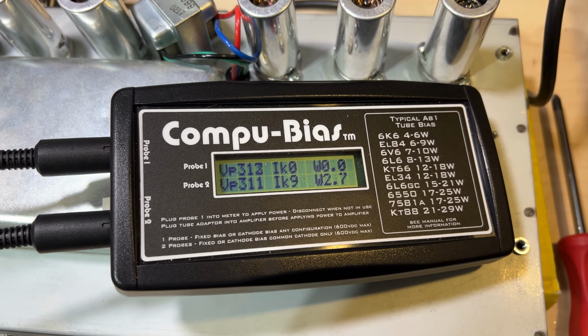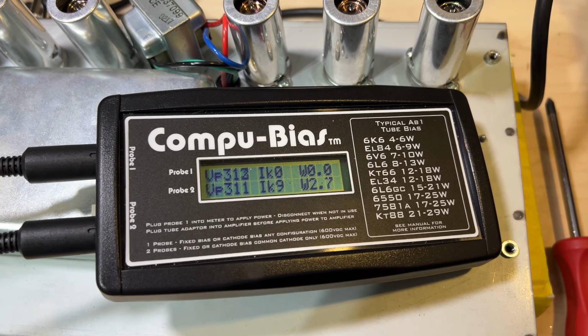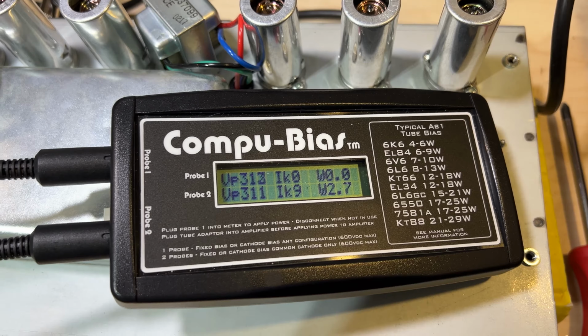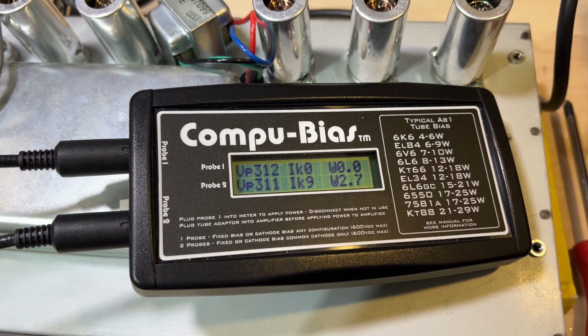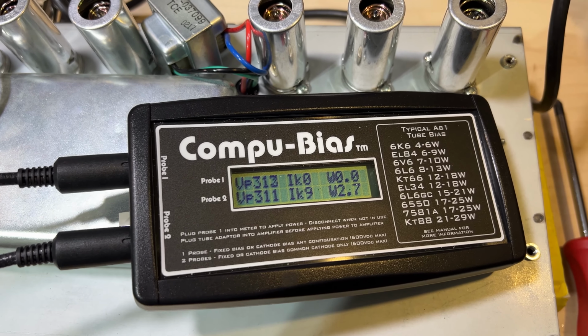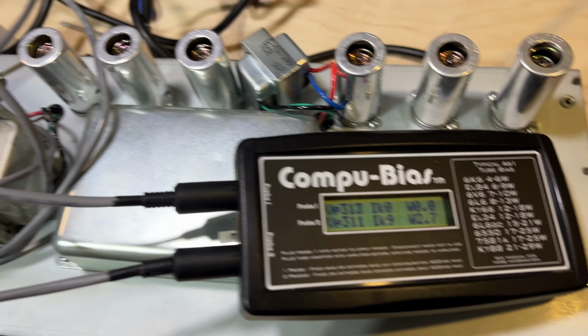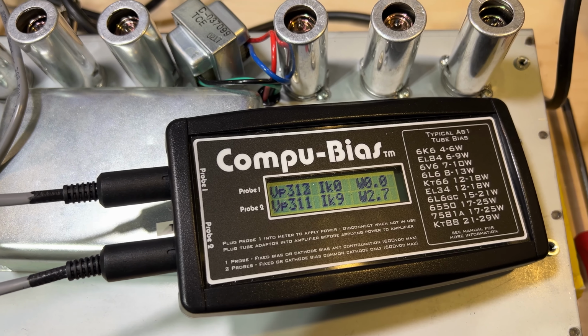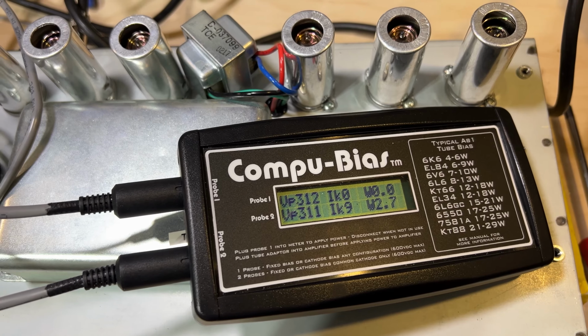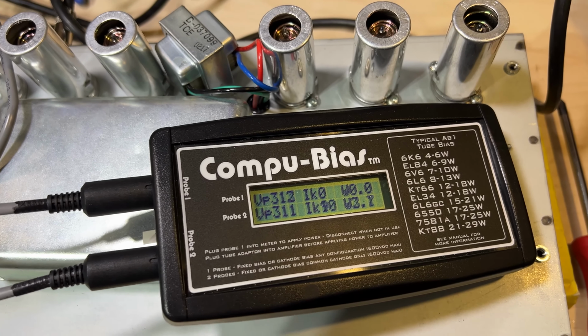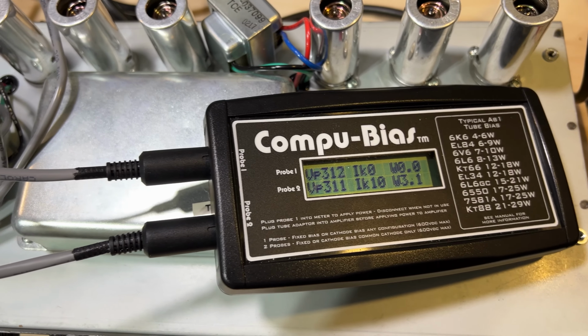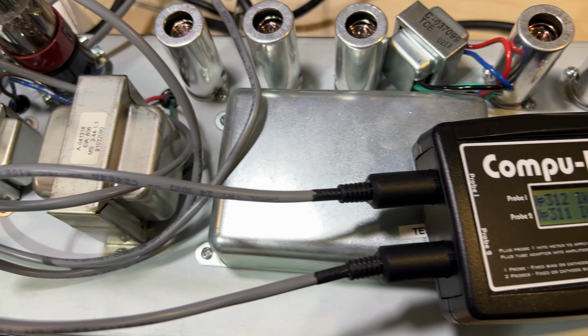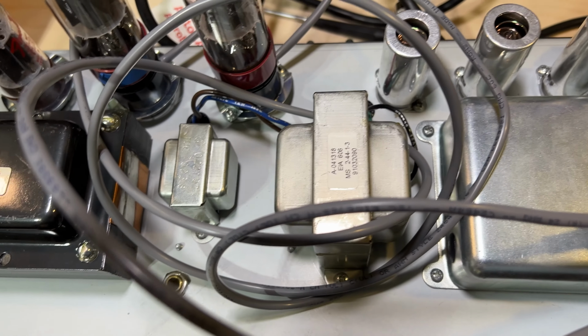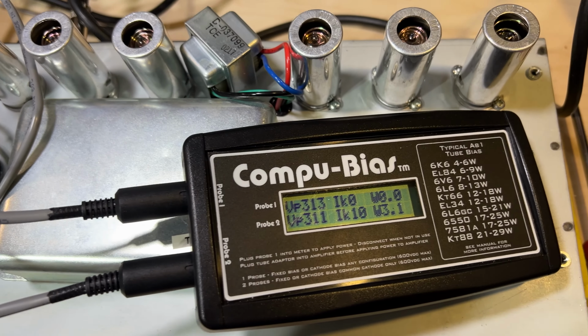Two ways to do this. If this was a failed short tube, we would get so much current being pulled through it that it would cause issues. But this is a unique situation where we can do a test with our bias meter as well as with our, I believe the B&K Dyna-Quik is what we call a transconductance tube tester. Someone maybe has better information on that. It's been a while since I looked up what that thing's actually doing, but it seems to be working pretty well.